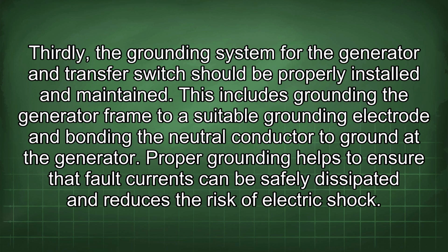Thirdly, the grounding system for the generator and transfer switch should be properly installed and maintained. This includes grounding the generator frame to a suitable grounding electrode and bonding the neutral conductor to ground at the generator. Proper grounding helps to ensure that fault currents can be safely dissipated and reduces the risk of electric shock.